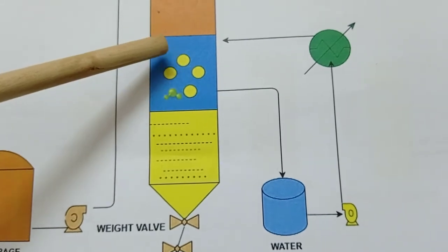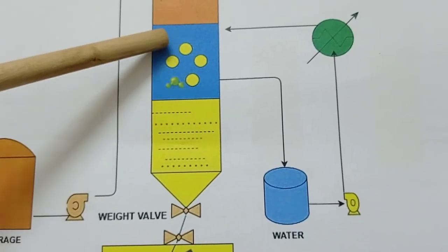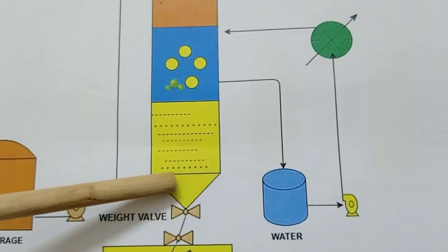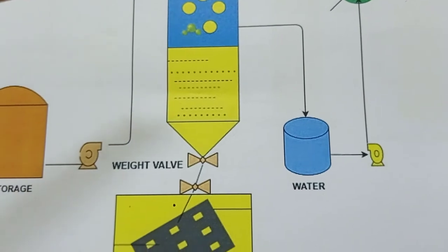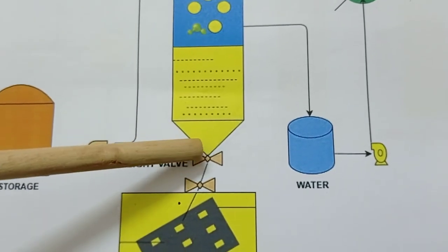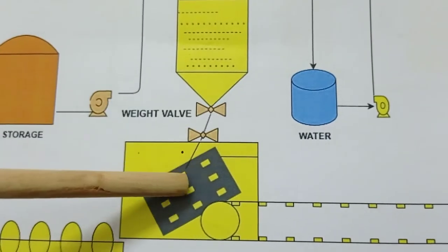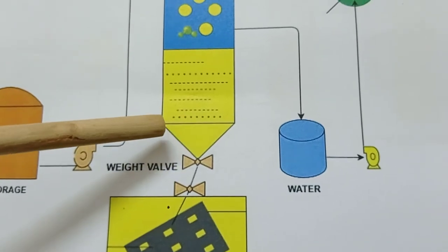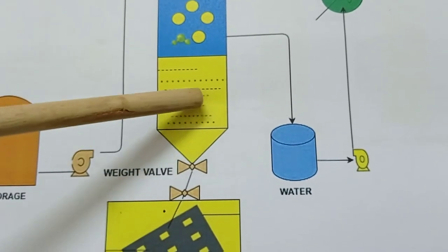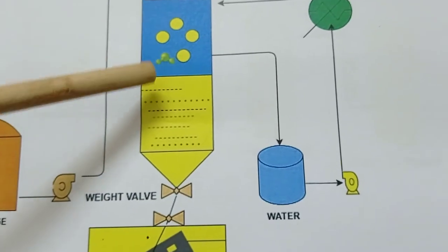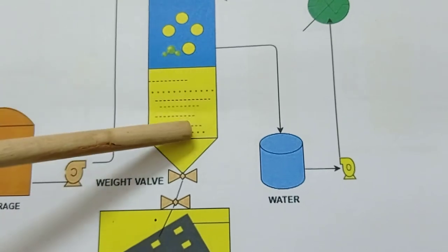Once the sulfur enters the water bath it forms a spherical or circular shape and gets collected at the bottom. This collection point has what is called a weight valve. The weight valve works on weight: we set an exact weight threshold, and when the accumulated sulfur exceeds that weight, the valve opens and sulfur is discharged to the vibratory screen. When weight reduces, the valve closes again.